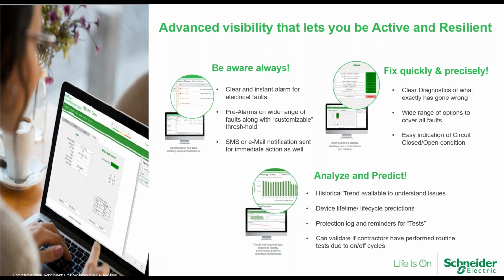It allows you to analyze and predict, because we've got the ability to have historical trend to understand what's going on. We can really start to predict what's happening in that system. It gives us device lifetime and life cycle predictions, protection logs, and even reminders for tests. It can even validate if you've done the routine test due to the on-off cycles. So it's a real fantastic system to really validate some of the works and installation and routine tests that have been done.